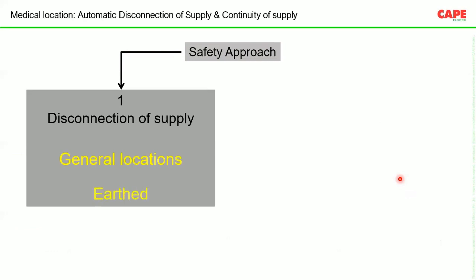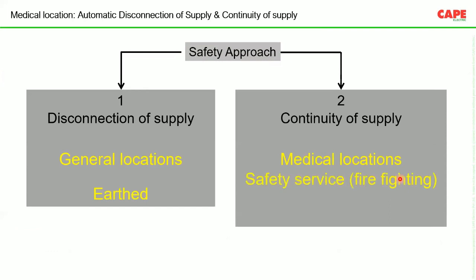Now, with respect to the concept, most of you know very well, because I am explaining this safety measure in almost every electrical safety class. In the concept of safety, there are 2 concepts. The first one is called the earthed power supply, which is for general locations where protective equipotential bonding and disconnection of the supply is mandatory. Whereas concept number 2 is for medical locations or for safety services, where unearthed supply can be used.